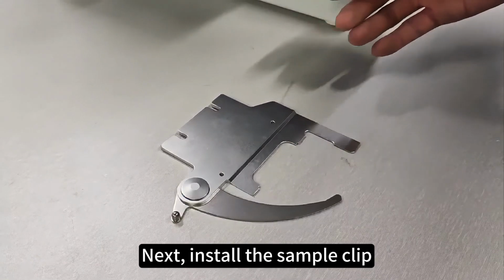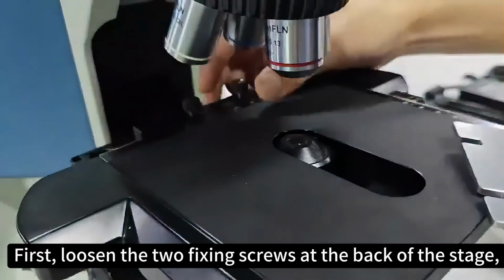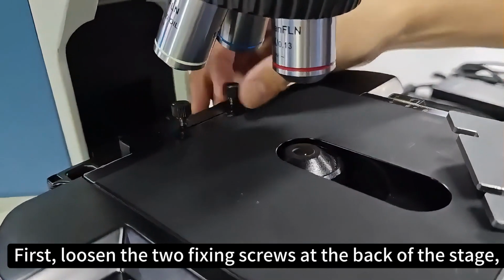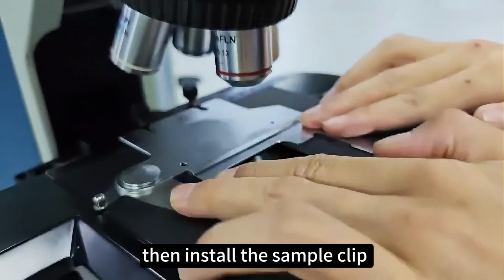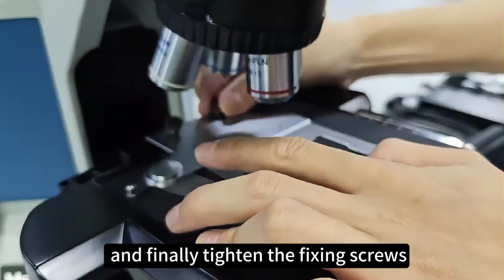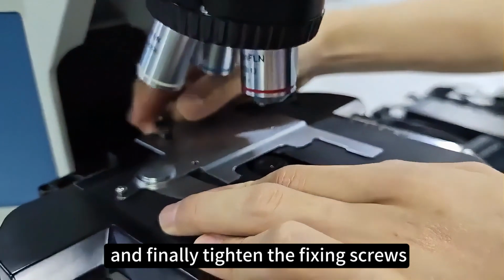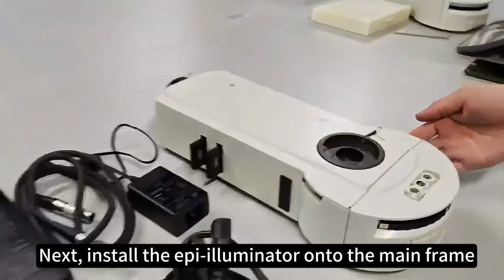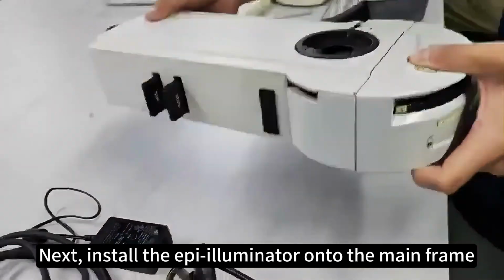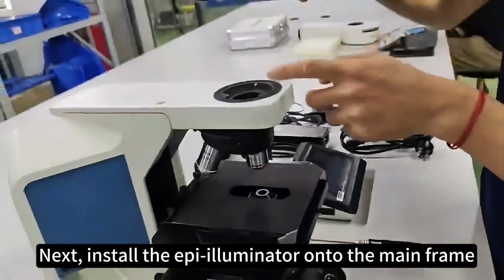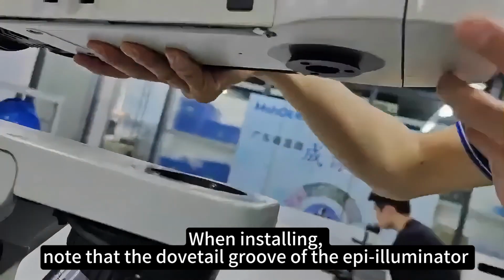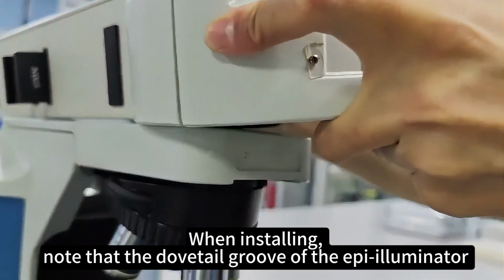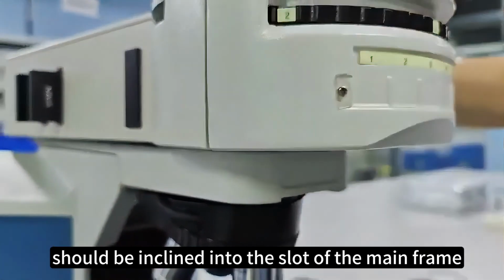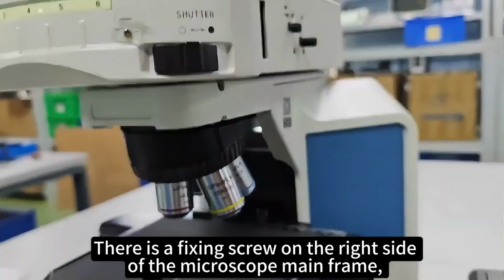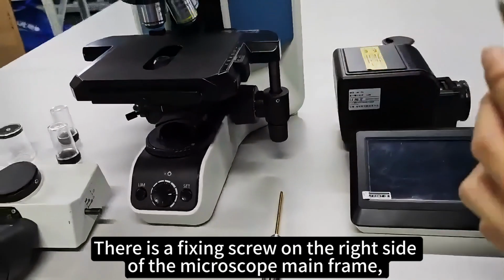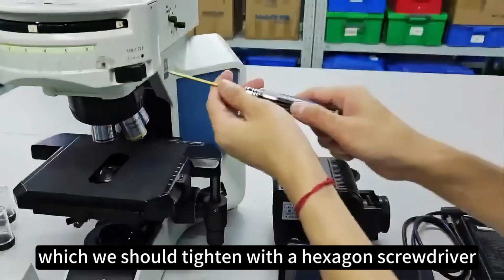Next, install the sample clip. First, loosen the 2 fixing screws at the back of the stage. Then install the sample clip. And finally, tighten the fixing screws. Next, install the epi illuminator onto the main frame. When installing, note that the dovetail groove of the epi illuminator should be inclined into the slot of the main frame. There is a fixing screw on the right side of the microscope main frame, which we should tighten with a hexagon screwdriver.